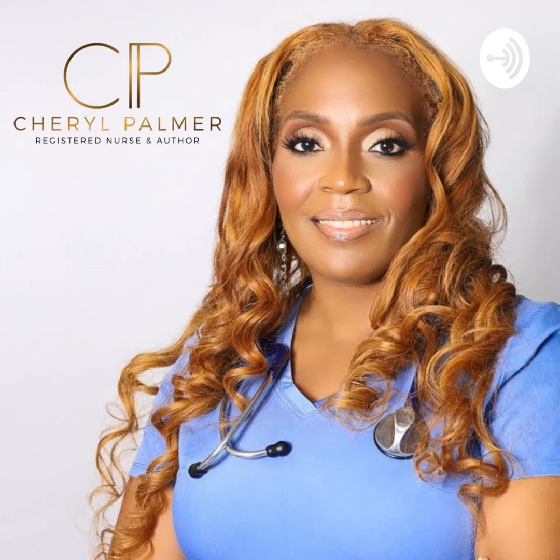If the balloon ruptures, it's a critical situation that requires immediate attention to ensure patient safety. Here are the steps that you should take. Assess the patient, check the vital signs and overall status, look for signs of distress, changing consciousness, or other symptoms that may indicate acute change in their condition. Verify the problem as always, confirm that the balloon has indeed ruptured. Typically, the balloon console will show alarms for high residual volume or low augmentation, suggesting a rupture. You may also see a sudden loss of diastolic augmentation on the arterial pressure waveform.